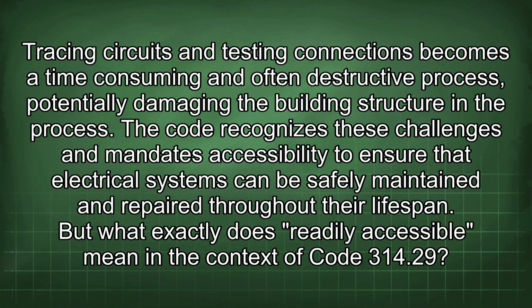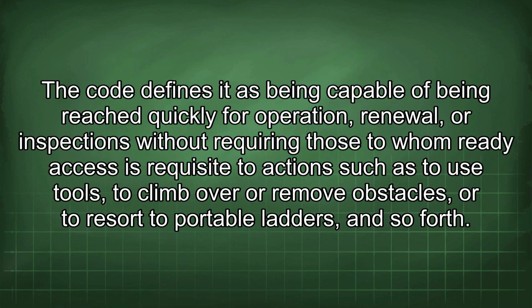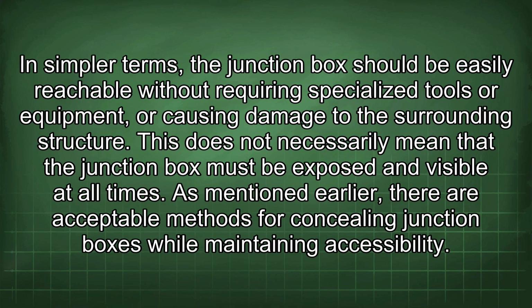But what exactly does readily accessible mean in the context of Code 314.29? The code defines it as being capable of being reached quickly for operation, renewal, or inspections without requiring those to whom ready access is requisite to action, such as to use tools, to climb over or remove obstacles, or to resort to portable ladders, and so forth. In simpler terms, the junction box should be easily reachable without requiring specialized tools or equipment, or causing damage to the surrounding structure. This does not necessarily mean that the junction box must be exposed and visible at all times.